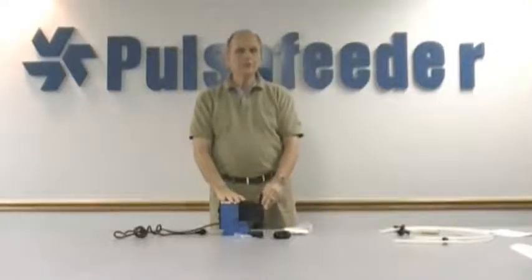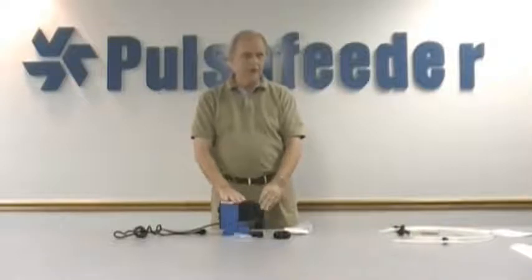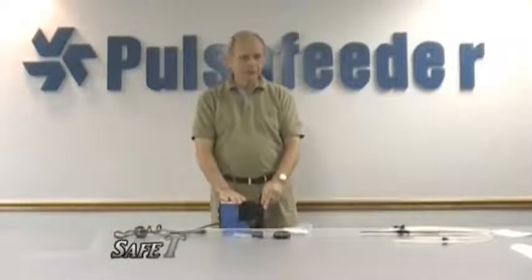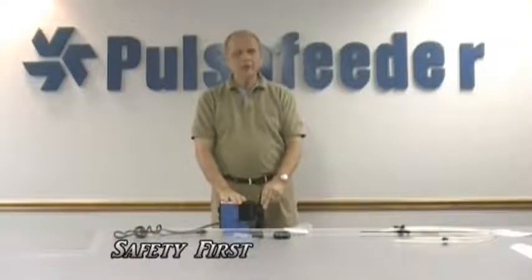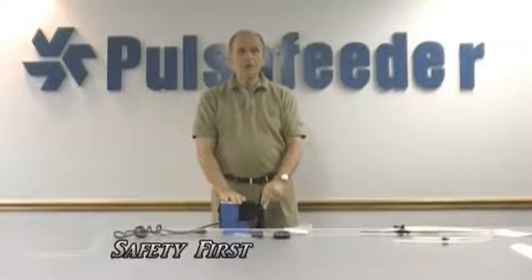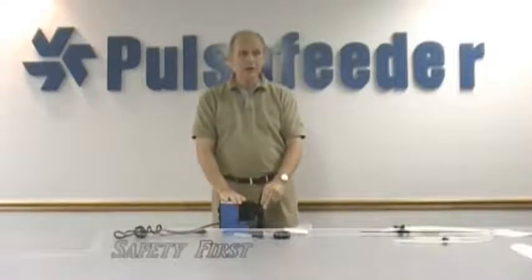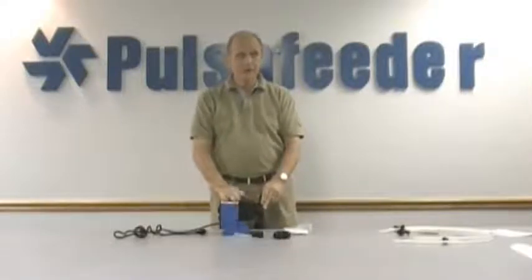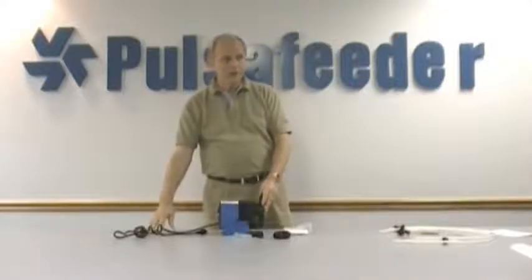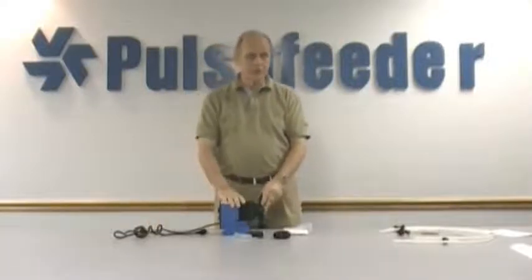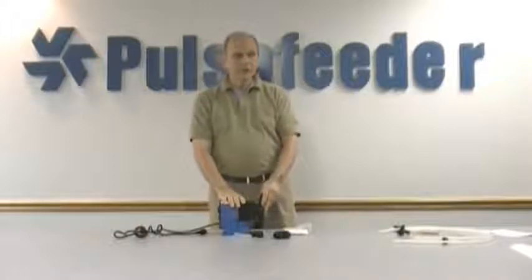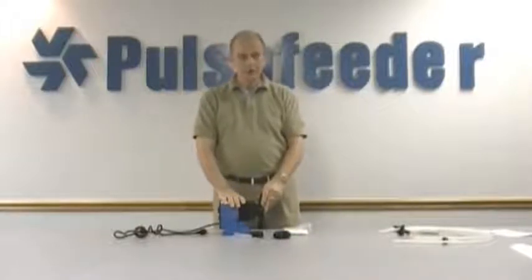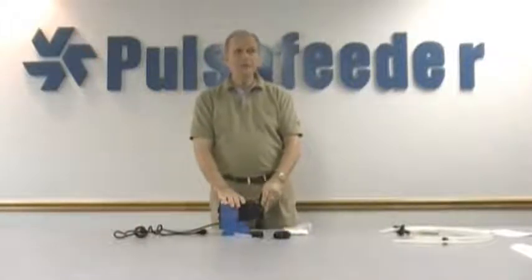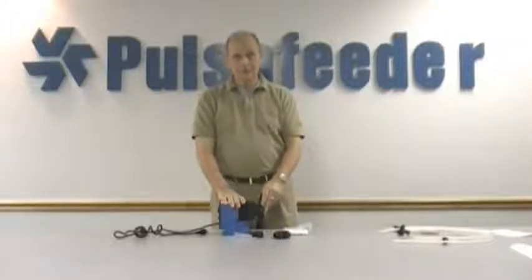Prior to using the COP kit and installing the parts, you need to have appropriate safety equipment. Check the MSDS sheet for the chemical you're using to know if you need safety glasses, gloves, etc. First, unplug the pump and release the system pressure. Then flush the system of all chemicals. Finally, disconnect the tubing or piping.